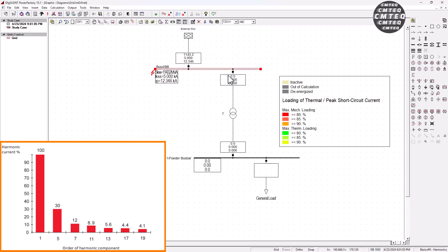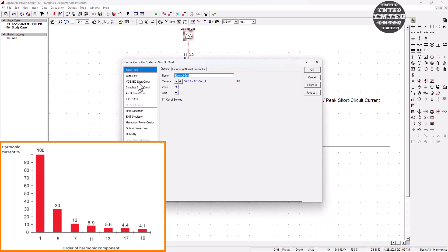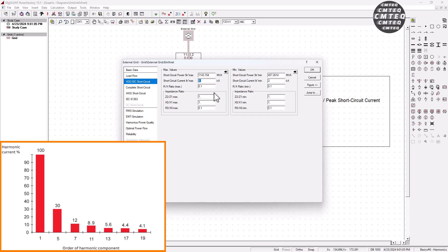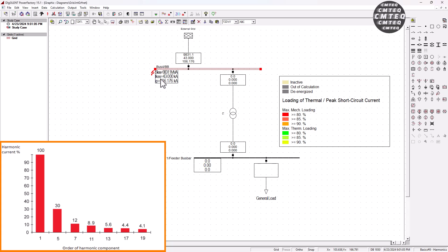The first point is the relationship between the generator maximum short circuit current and its internal impedance. Here we've got 5 kilo-amps of maximum short circuit current for this generator. When we execute the maximum short circuit current calculation, we get 5 kilo-amps of short circuit current on the generator bus bar. These 5 kilo-amps is related to the generator internal impedance — a higher short circuit current means a lower impedance, and a lower short circuit current means a higher impedance. If we change this back to 43 kilo-amps and execute the short circuit calculation, we get 43 kilo-amps, meaning there is a lower impedance on the generator.